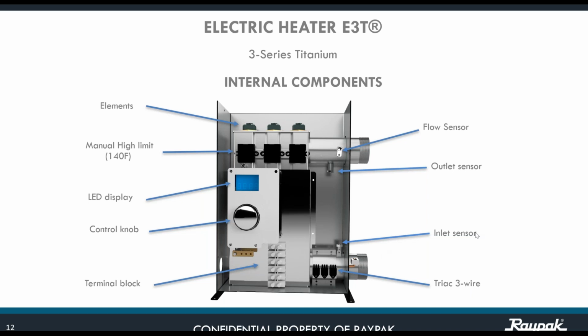Okay, the inlet sensor, because we monitor the inlet temperature, and the outlet sensor temperature. Remember, this is a flow sensor. It is not a flow switch. It is not a pressure switch. If you can imagine a propeller inside of that particular point, when it starts to receive the minimum gallons per minute that we are about to see, it starts to rotate, and it's going to stay like that for 1 minute without doing anything. And then once that 1 minute has passed, it's going to send a signal to the CPU. CPU starts to move voltage around the unit.